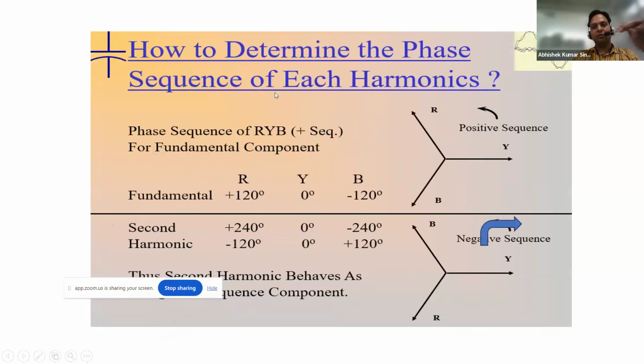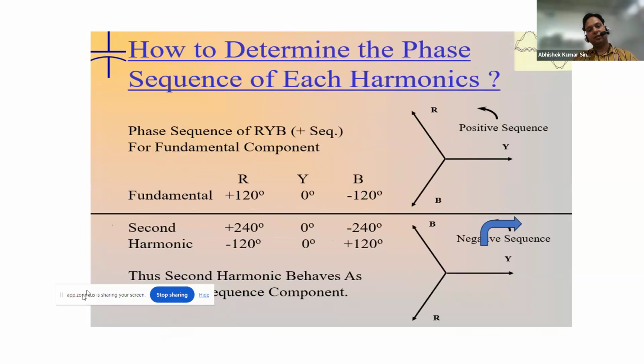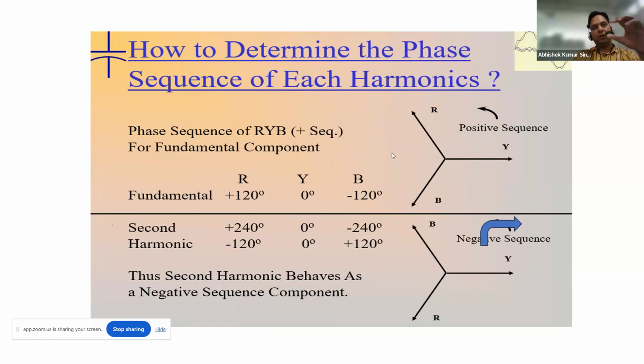Now, how to determine the phase sequence of each harmonic? As we discussed, whenever there is an anti-clockwise rotation, that sequence will be a positive sequence, and when there is a clockwise rotation, it will be a negative sequence. This you can note, or I believe you must know this. If you see here, this is the reference point, and this is the angle of 120 degree, this is 120 degree, and this is 120 degree. So this is the fundamental. All three phases are separated from each other by a 120 degree angle. Now this is the second harmonic. In the second harmonic it is 240. 240 means negative.